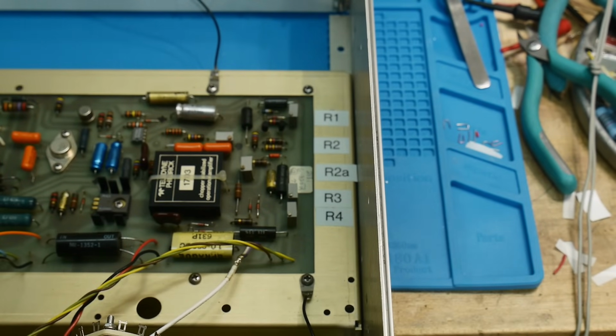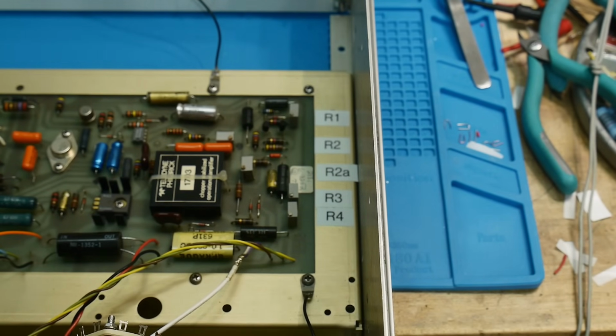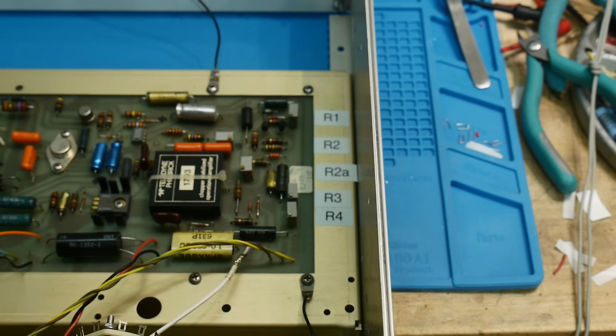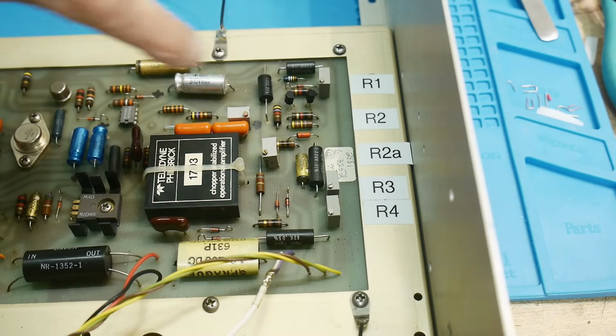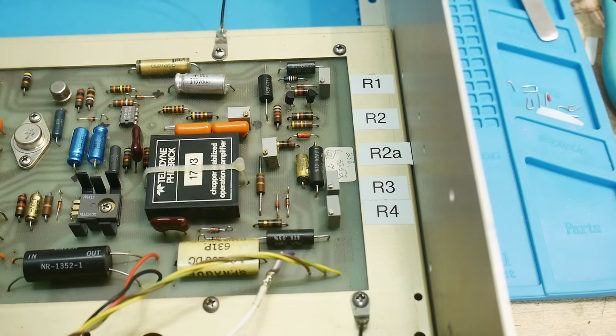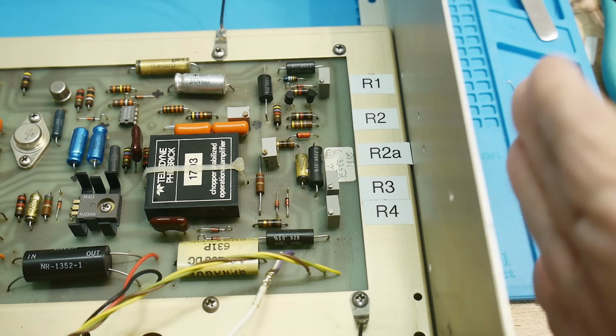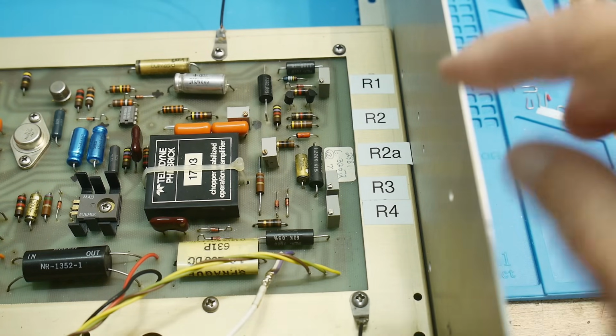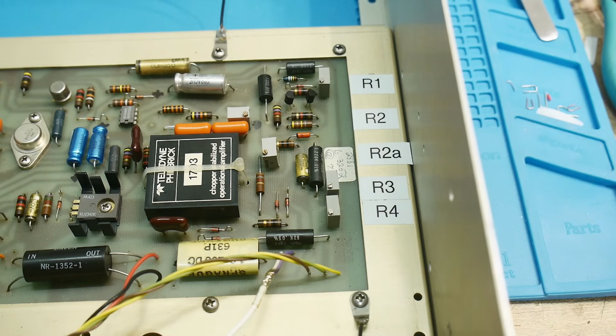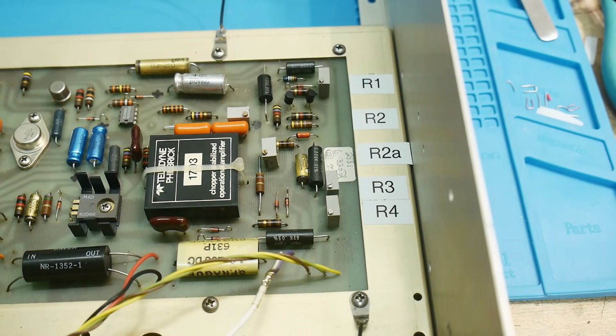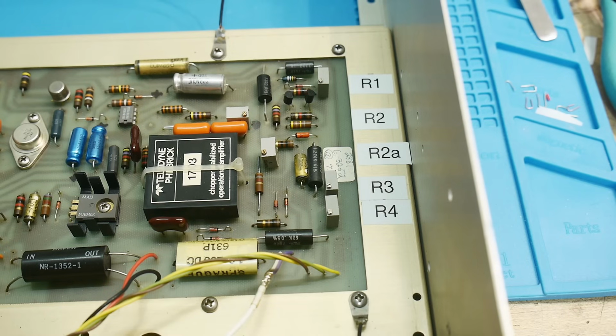And so what we want in an instrument like this is to be very stable with temperature. So we want to have that perfect diode, a diode that has no temperature coefficient at all, right? So let me show you that. This is my Zener diode, and handwritten on a note inside of the instrument, it says 6.3252. So that diode is magic at 6.3252. That's where this company spent time and energy characterizing diodes and figured out exactly where you should operate this diode. One of the reasons these boxes are expensive is that they took the time and energy to make perfect diodes, right? They bought a bunch of diodes and then they characterized them all.